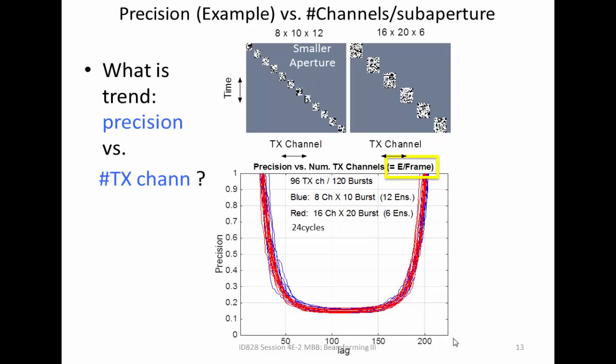We'd like to look at the effect of increasing the number of channels processed or transmitted simultaneously, and what effect that has on precision. If we normalize for equal energy per frame, the precision is about the same, but we're reducing the transmit voltage by the square root of the number of channels shot simultaneously. This has implications for tissue motion — how many channels do you want to transmit simultaneously? We tried smaller apertures to see if they would behave differently under tissue motion.